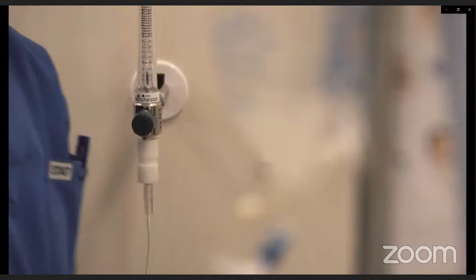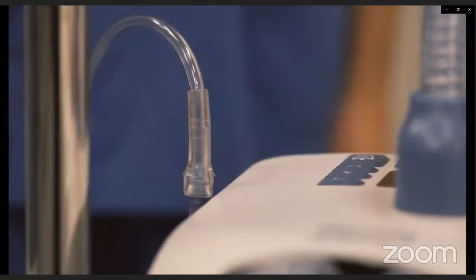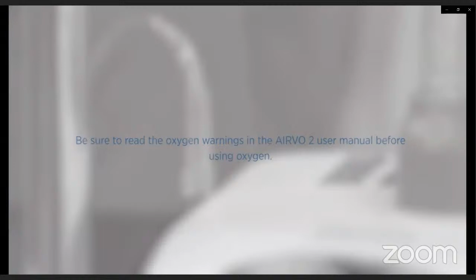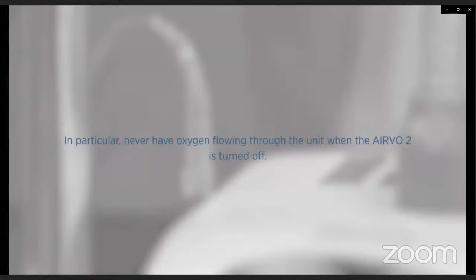For patients that require oxygen as part of their treatment, you can connect the wall supply to the oxygen inlet port on the side of the unit now. Make sure you push the oxygen tube firmly onto this connection port. Be sure to read the oxygen warnings in the AIRVO 2 user manual before using oxygen. In particular, never have oxygen flowing through the unit when the AIRVO 2 is turned off.